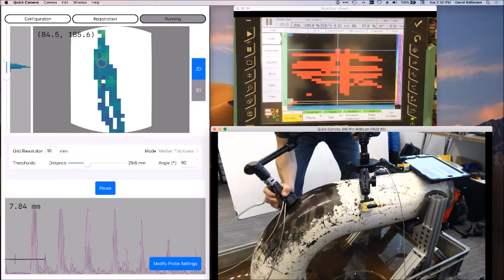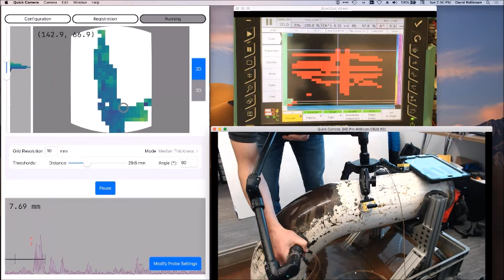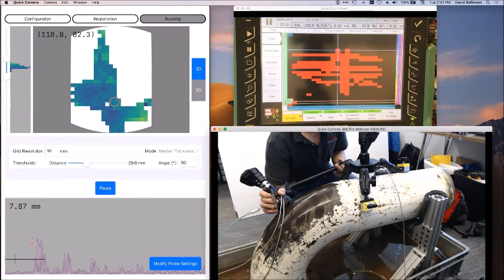And our approach to data in this mode is a little bit different from what traditional flaw detectors do, where the data is always associated with the grid, and only one grid cell can ever have a thickness value associated with it. What we're doing is we're essentially measuring all the data online, and we're still displaying a single number to the operator, but it is either the average, or the median value, or the max value, or the min value that you saw within that cell.